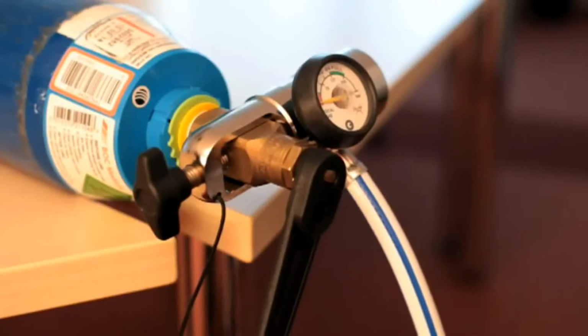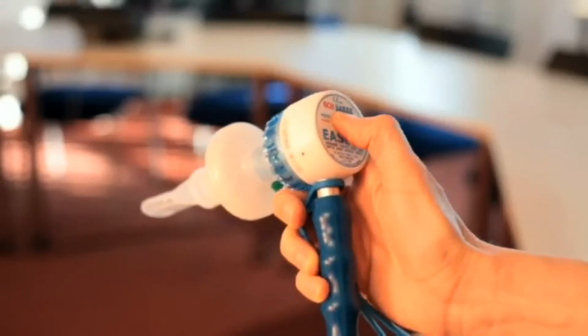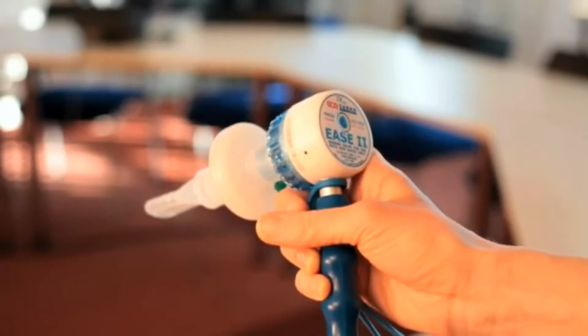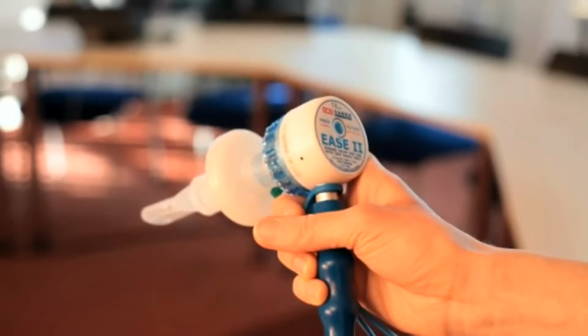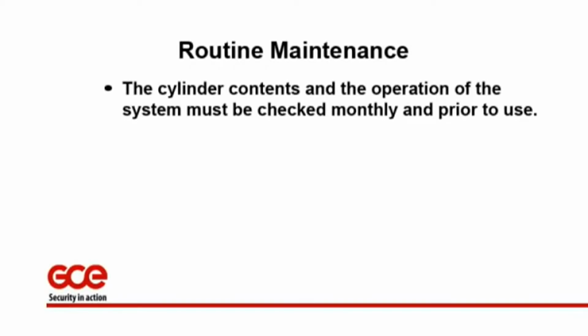When treatment has been completed, close the cylinder valve and operate the test button to depressurize the system. Clean the system as described in the attached cleaning label. The cylinder contents and the operation of the system must be checked monthly and prior to use.